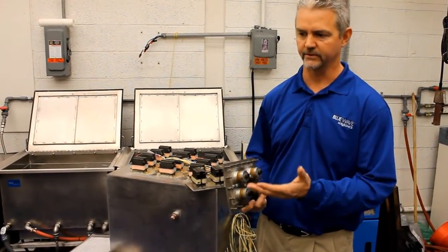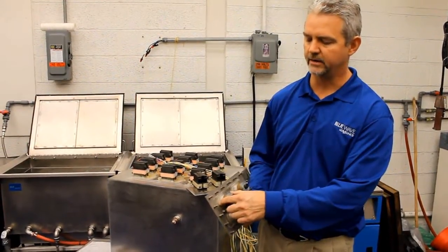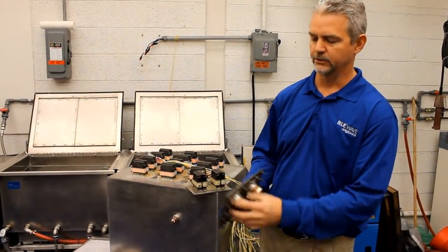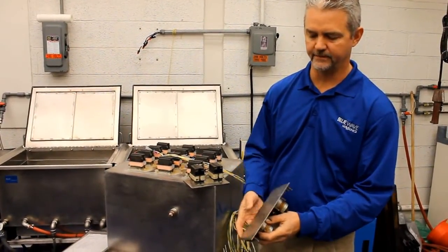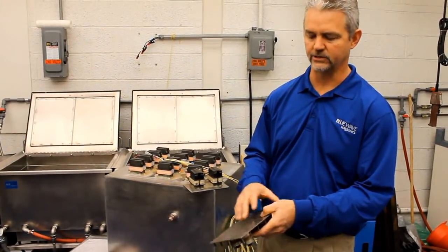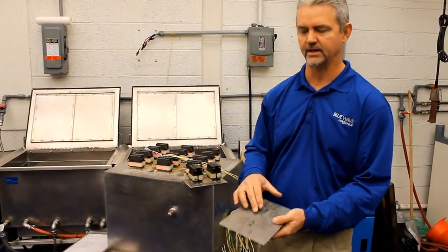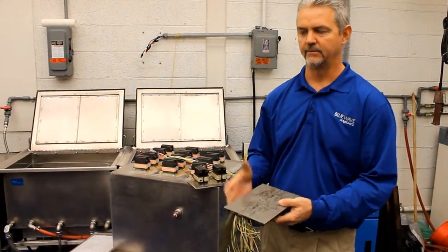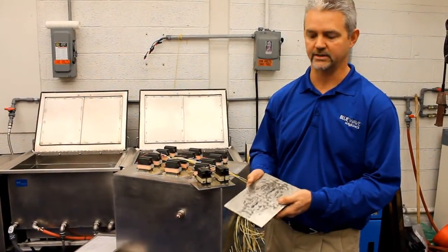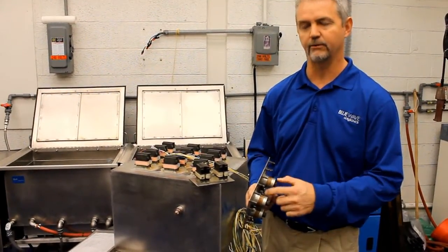There are several other problems with this particular design in that it's epoxy bonded onto the radiating diaphragm, which eventually becomes the bottom of the tank. This diaphragm is fairly thin and can get cavitation erosion. It will actually wear through this diaphragm due to this erosion process, which is going to happen on an ultrasonic tank because of the cavitation. If it's a very thin diaphragm, it will pit through.